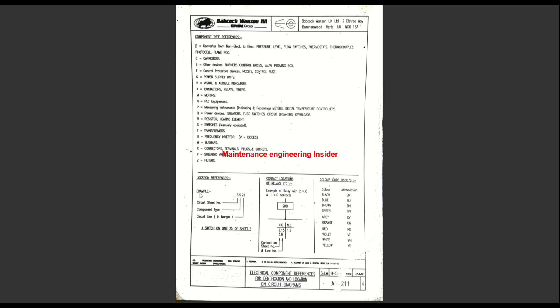This is the information you need. Once you know what all these letters and numbers mean, you can troubleshoot from any wiring diagram. Remember: three is the sheet number — not the page, but the diagram number. The electrical diagram number tells you this is foglio three of twenty — either in Spanish, French, Portuguese, Italian, or in English it would say 'sheet.' So this is a switch on line 25 of sheet three — that's what it is saying here.